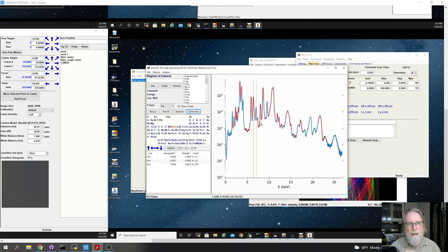So a 7 keV x-ray hits the silicon, that creates some amount of charge. A 14 keV x-ray hits the silicon, and that will create twice as much charge and be swept out in the silicon diodes. But there's a problem for that because we have a lot of x-rays hitting the sample. In fact, if I plot total output counts, we have about 2 million counts entering the detector. And it takes a little bit of time for each of those x-ray energies to be measured for how much energy was in that current.